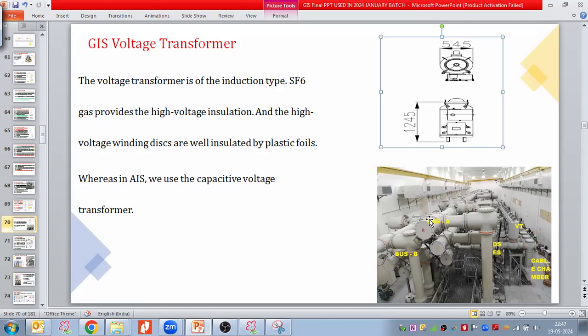So when we take the VT in the case of GIS, that would be the EMVT, electromagnetic voltage transformer, not the capacitor voltage transformer. The capacitor voltage transformer will come outside of the building, outside of the GIS hall, not inside. This VT is your EMVT, a simple voltage transformer. The surge arrestor, CVT, wave trap and transformer, these four equipment are outside equipment of the GIS, not inside. So this VT is EMVT.